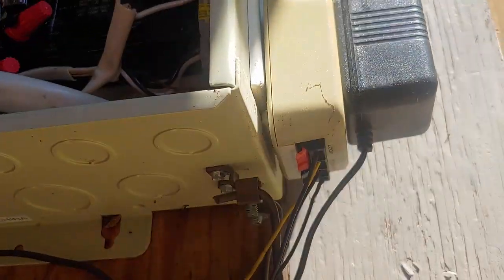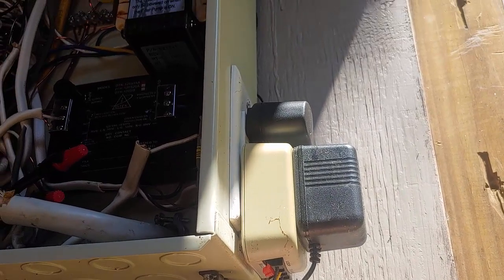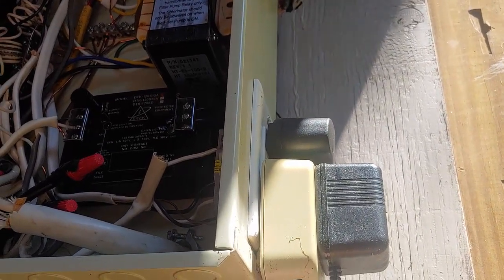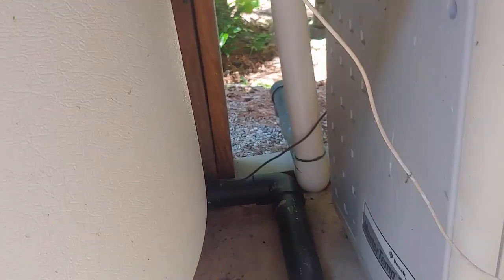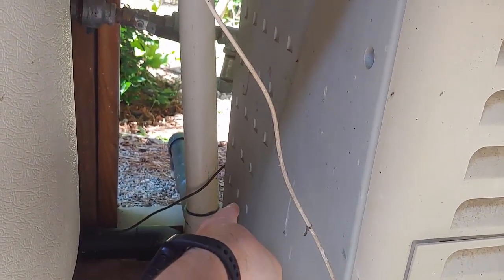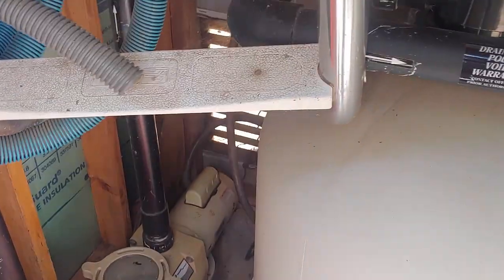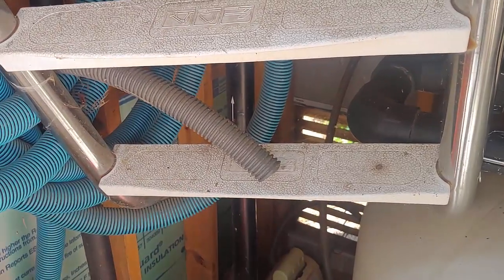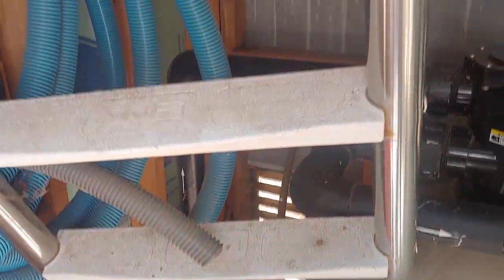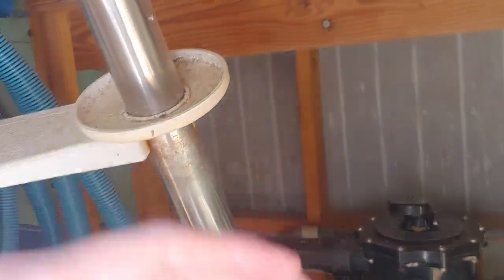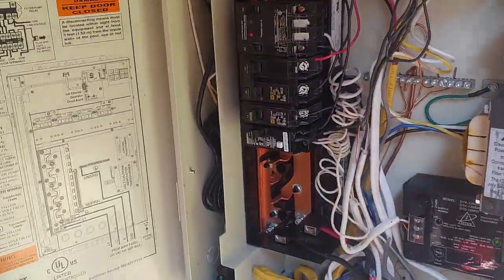This box is bonded to the entire system all the way around, with bonding lugs that enter the whole system, including your swimming pool and everything. This heater on my spa is bonded, and you can see the copper wire that carries through on a lug back there. It's also bonded to my pump, and then that goes into a grid that bonds my entire concrete around my pool. It also bonds when I have my ladder in, and the bonding system also bonds with the water. So the bonding system is very important. You don't want to overlook any of that.